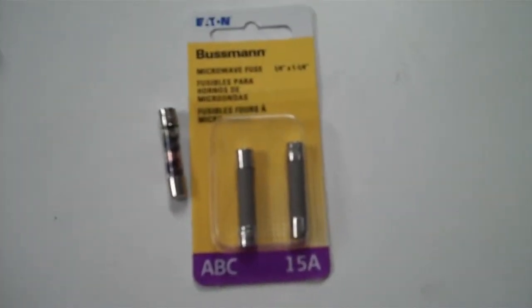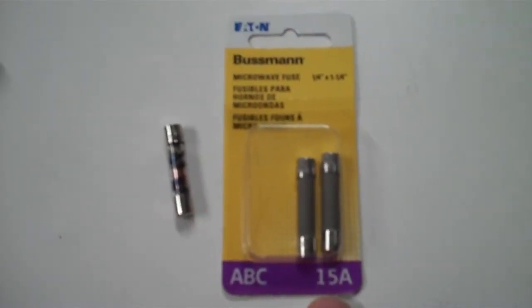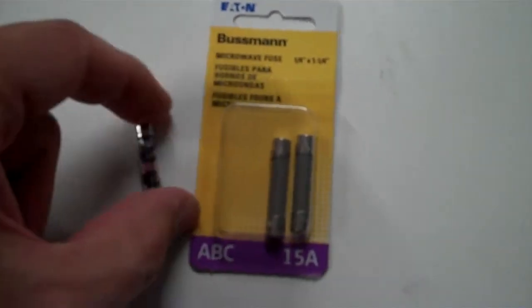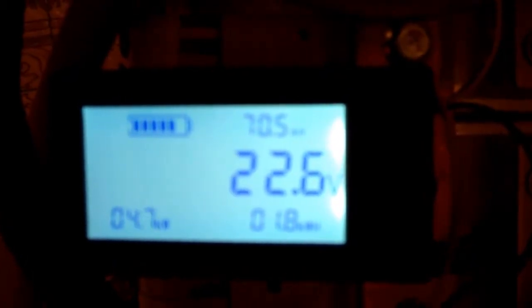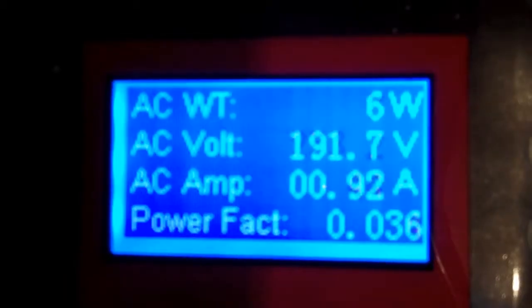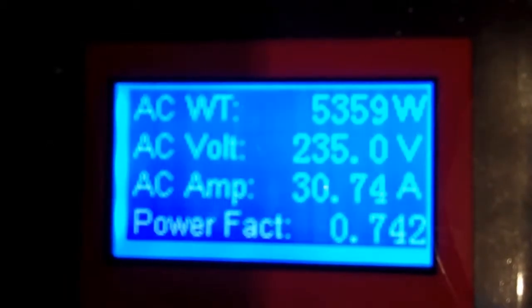Unfortunately, after the first time ran successfully, the second time it tried to start up the well pump, it blew a fuse. And then I had another fuse blow. So eventually I went to Lowe's, and these are 15 amp fuses. I bought a different 15 amp fuse that's a microwave fuse, and so far that fuse has not blown. However, it just transferred the problem to my DC circuit breaker. After the inverter draws more than 200 amps for multiple seconds, that DC circuit breaker flips off. So the inverter output displays that the well pump is drawing more than 5,000 watts for multiple seconds, and I verified this with a Power Sight meter.